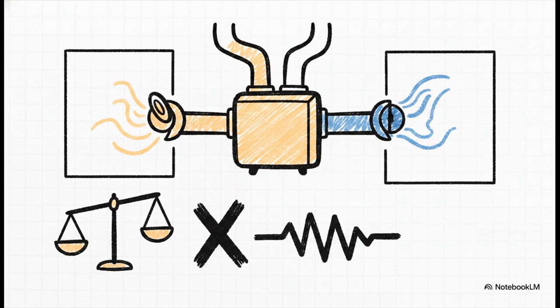So if your system is completely struggling to push air to those distant wings or upper floors, zoning can precisely target the airflow right to the zones crying out for it. If you're dealing with a system that's turning on and off rapidly, known as short cycling, or if the temperature keeps drifting, zone dampers actually step in to help. They tailor the airflow perfectly to match the indoor demand of that specific, separate world, stabilizing everything.